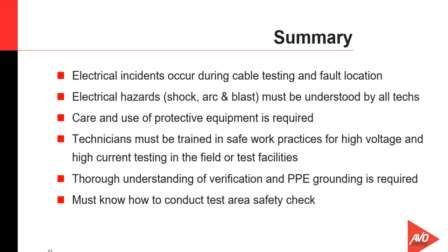Well, remember, we've already had a failure. We've already made an error because the grounds are now being asked to operate under a very severe condition, which would be maximum voltage fault energy. So we don't want another issue to happen and the grounds to burn up and cause a risk to the employees working there. We need to know how to conduct a test area safety check and to be able to understand when the test area has been safely set up, and that all the PPE items are there and everything that we need to conduct that series of tests has been validated. Okay, that kind of concludes our discussion.